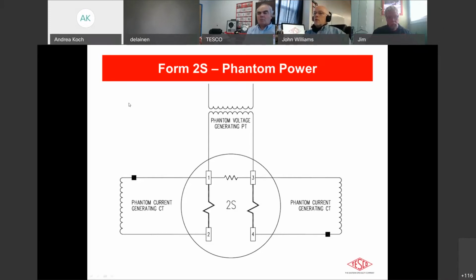Here we see the 2S application. I drew the potential transformer across the voltage coil here, and that is the case for a lot of test boards. When we apply voltage here, we actually do 2 potential transformers, one off of pin 1, one off of pin 3, and so we simulate that 120 volt, 180 degrees opposed on the voltage. And similarly, we match that with the currents.